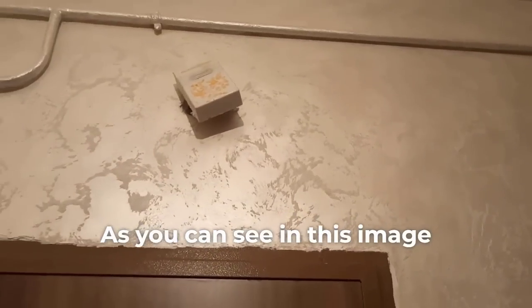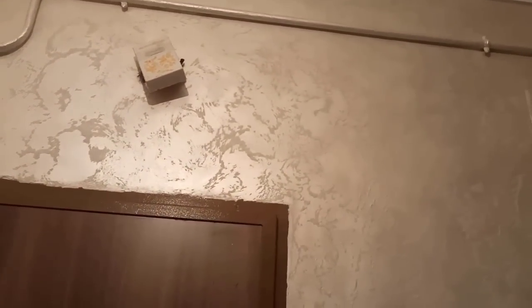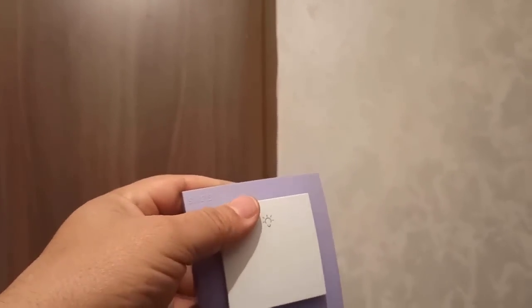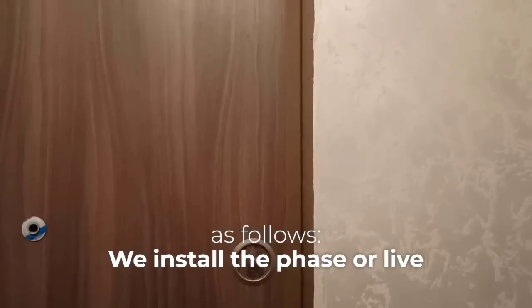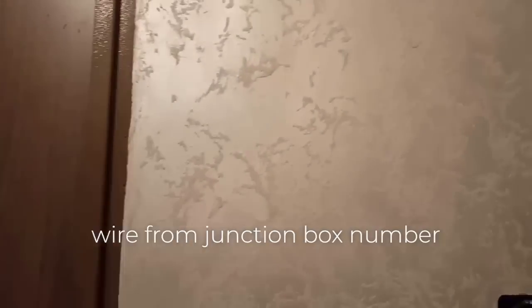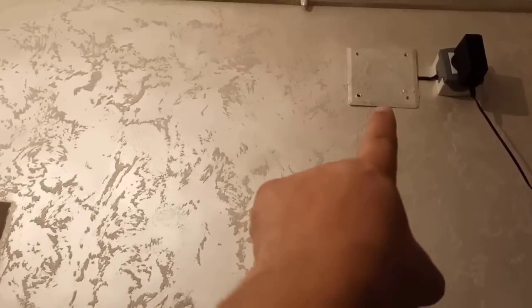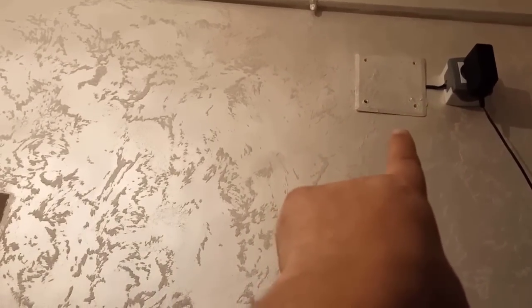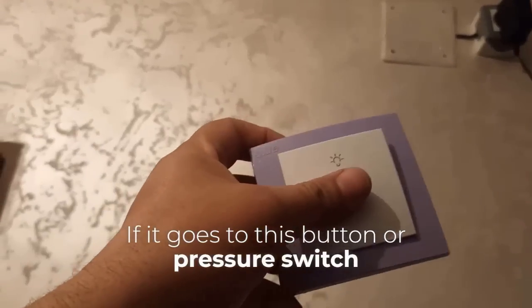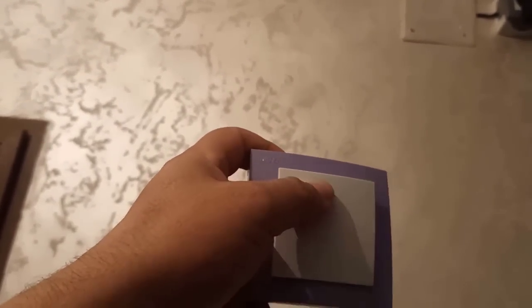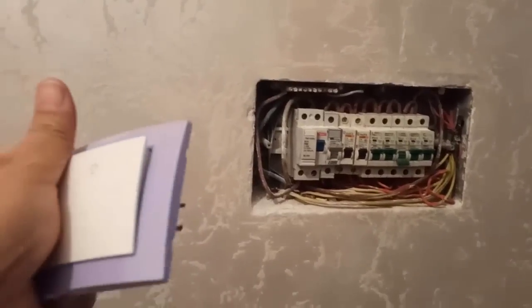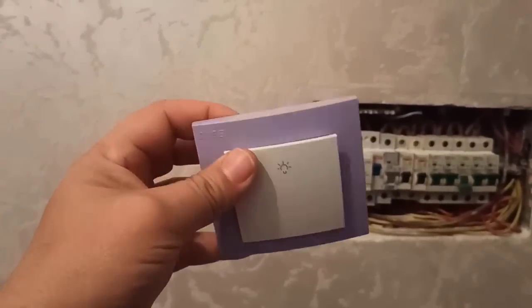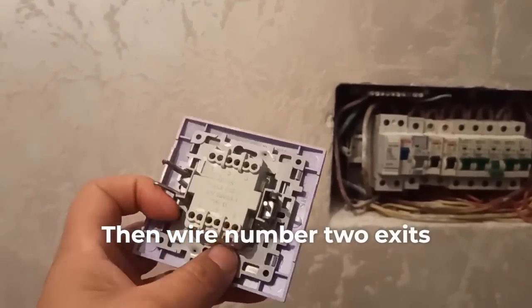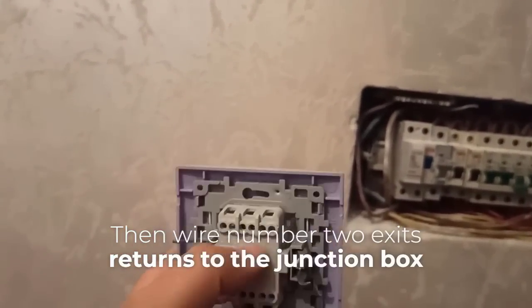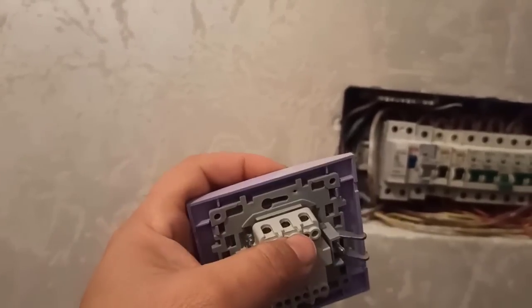As you can see in this image, how can we connect this bell? We see the button outside the door, so the connection method is as follows. We install the phase or live wire from junction box number 1. If it goes to this button or pressure switch, it goes to point number 1 here. Then wire number 2 exits, returns to the junction box, and then goes to this bell.